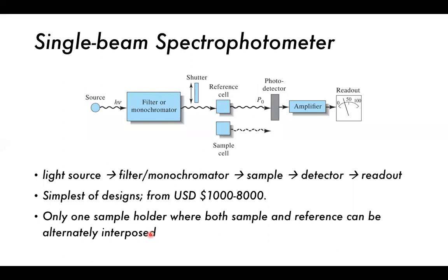This is a simple spectrometer for UV-Vis absorption spectroscopy. We have a light source on the left-hand side producing light of energy hν. This passes through a filter or monochromator to create a single wavelength of light, which is then shone onto our sample. We have a shutter which can turn the light on and off. Then we have a reference cell and a sample cell, usually on a lever which can be pushed in or out, allowing a particular cell to be in the path or not.